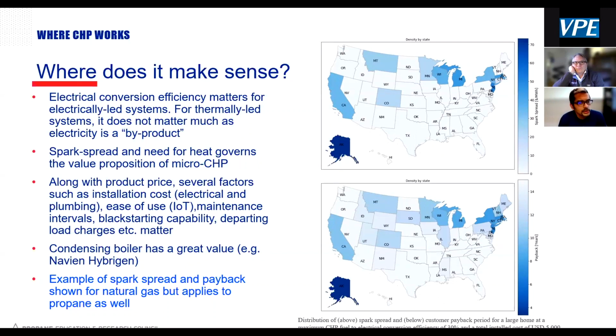The chart on top shows the spark spread, and the chart at the bottom shows the payback. Higher the spark spread, say take a number like 70, lower is the payback period. So it's the other way around: higher the spark spread, lower the payback period, and a customer wants a lower payback period.